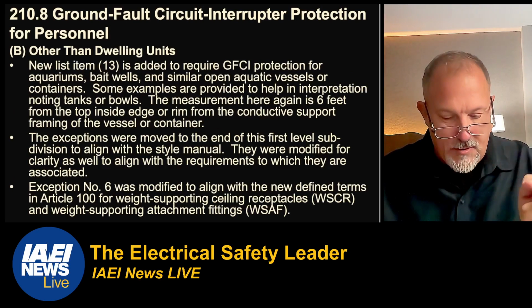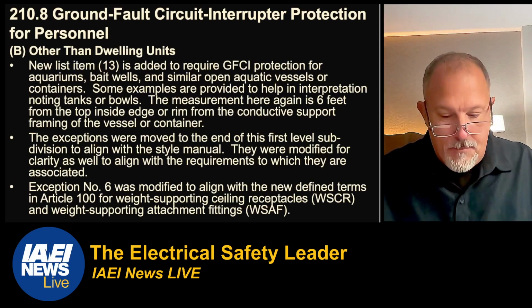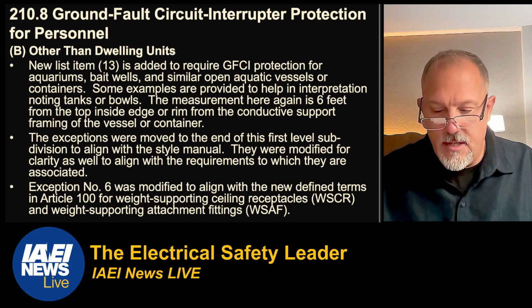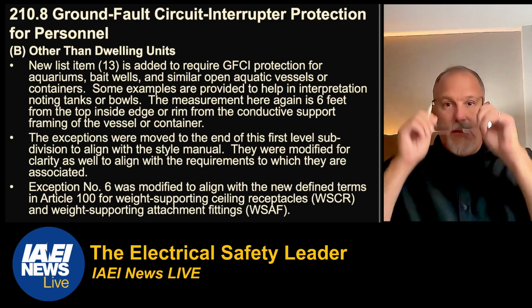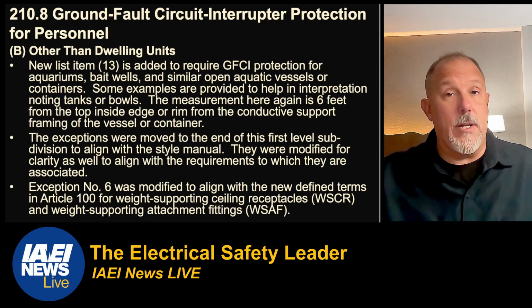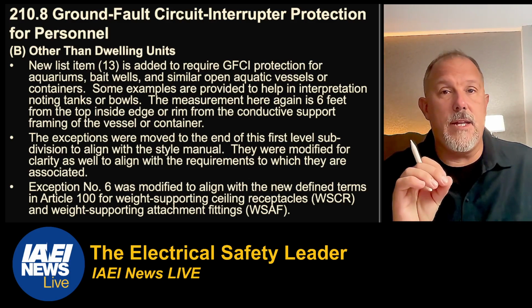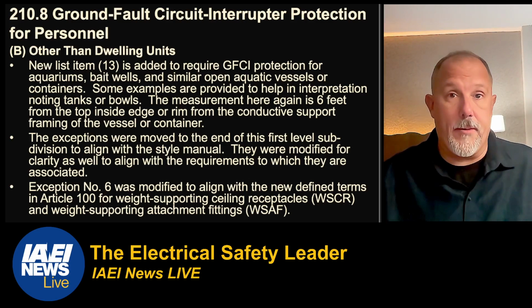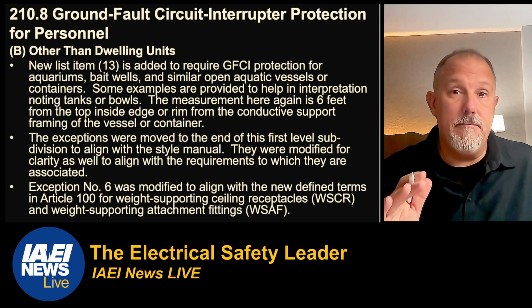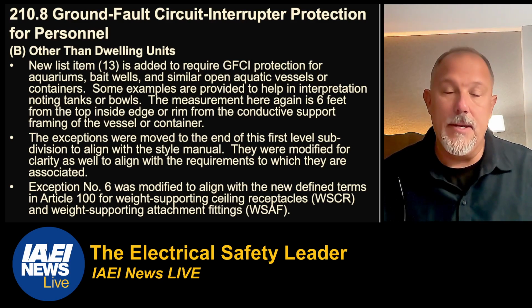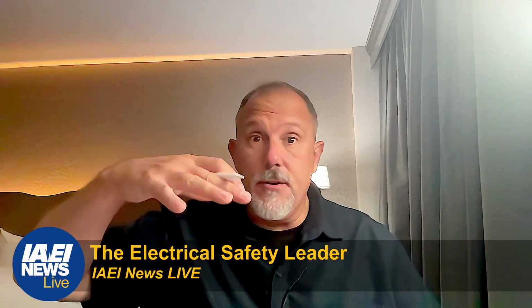But then list item 13 is new. Aquariums, bait wells, and similar open aquatic vessels or containers, such as tanks or bowls where receptacles are installed within 6 foot. Now, this is one of those that would be hard to migrate over to a dwelling unit, for the reason that you don't know where someone's going to put an aquarium. But I know I had an aquarium, and you think about there's a heater, right, that's plugged into the wall outlet, and that heater, where does it go? Directly in the water. And there's a pump, but the unit I had was down and it was plastic tubing. So the heater though, directly in the water.